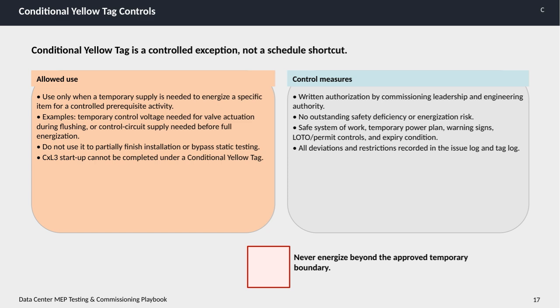Also, full system startup, especially commissioning level 3, cannot be completed while under a conditional yellow tag. Now, let's talk about the control measures in place to ensure safety and compliance. Authorization must come in writing from both commissioning leadership and the engineering authority. There cannot be any outstanding safety deficiencies or energization risks associated with the equipment. Additionally, a safe system of work must be established, which includes a temporary power plan, clear warning signage, lockout/tagout and permit controls, and an explicit expiry condition for tag.